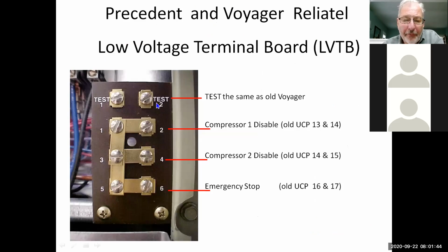And there's a couple of different ways you can do it. Now you can put a jumper on there and leave it there. And what it will do is it will put it in test mode and drive it through every 30 seconds. So test 1 is going to be fan, test 2 is going to be economizer, then it's going to go compressor 1, compressor 2, then it's going to go to heat. It'll go to switchover valve if it's a dehumidification unit, but every 30 seconds it will drive it through if you leave your jumper on there.